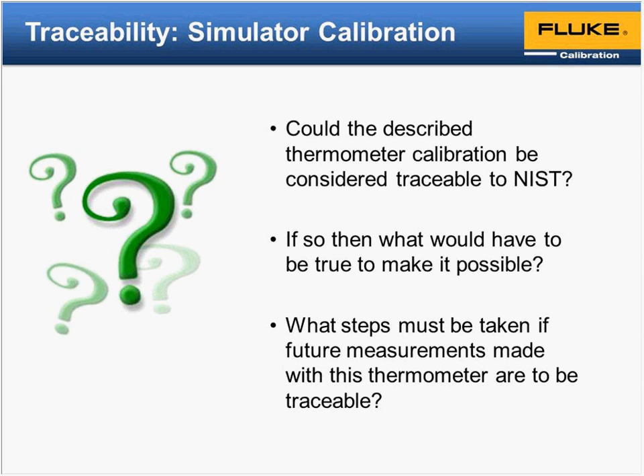So the questionable piece at this time is the probe. And from a few slides back, we stated that potentially 75% of the error could be contributed by a bad probe if it's in your process. So even if you're reading the resistance very accurately, you could still have a probe that's not conforming to the curve that we wanted to see. So if we were to make this truly traceable, we would definitely have to put both pieces together and do a calibration that way. That's more we'll build on going forward.